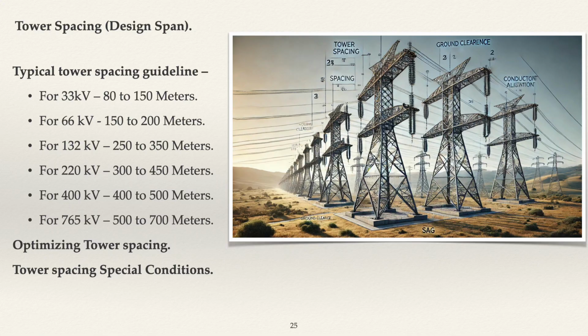Typical tower spacing guideline: for 33 kV, 80 to 150 meters. For 66 kV, 150 to 200 meters. For 132 kV, 250 to 350 meters. For 220 kV, 300 to 450 meters. For 400 kV, 400 to 500 meters. For 765 kV, 500 to 700 meters. Note, actual spacing may vary depending on terrain, conductor spacing, and other factors.